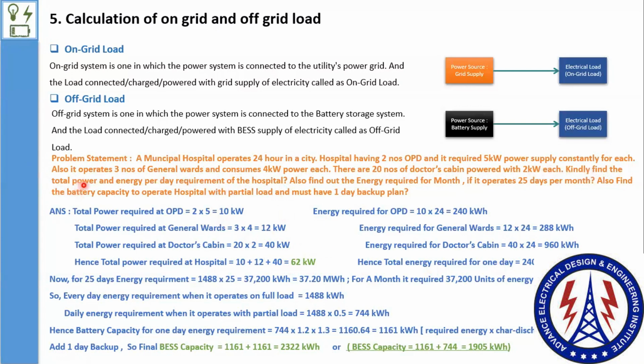Kindly find the total power and energy per day requirement of the hospital - is this the resultant? For 1 day, they require 1488 units to operate the hospital for 24 hours, and the peak power is 62. Nothing much - it's a sum of all the loads with their peak powers, and the sum of their loading plus operating time results into the energy.